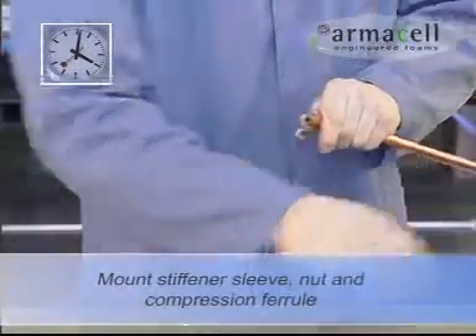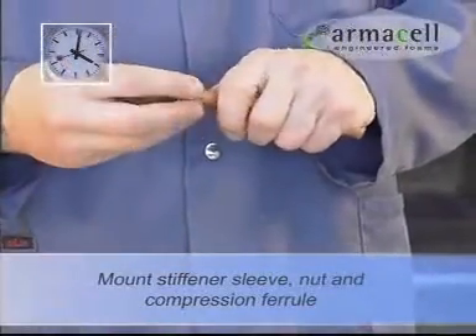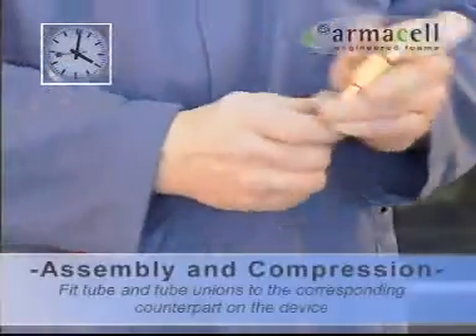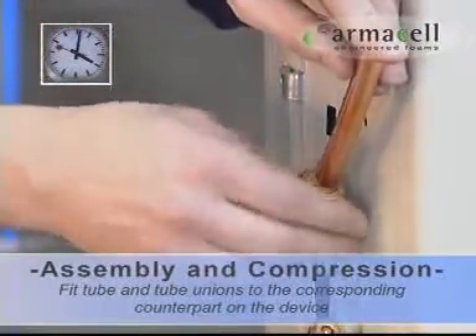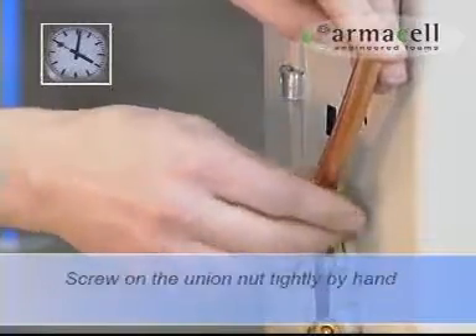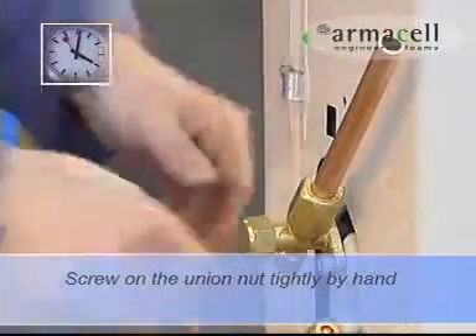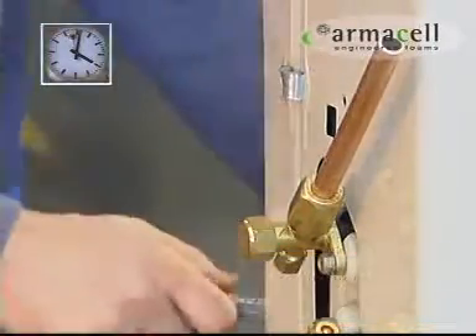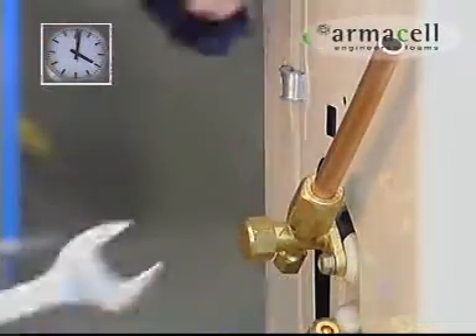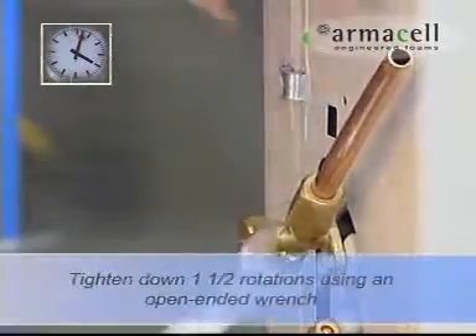Insert the stiffener sleeve into the copper tube and mount the nut and compression ferrule. Now position the union on its counterpart on the device. Screw on the union nut by hand until finger tight. Tighten down with an open ended wrench exactly one and a half rotations.